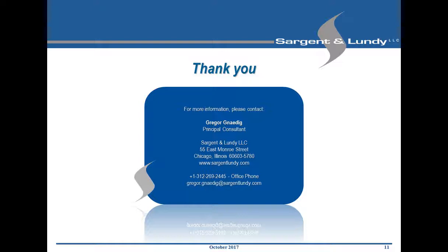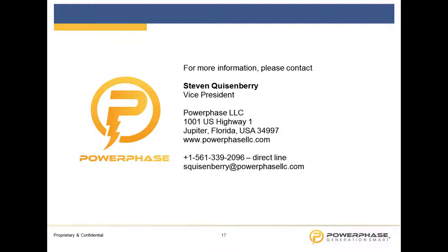Okay, great. If we just switch back to you, Steve, the question is, how many installations with F-class gas turbines have you done? Sure. So the first F-class install was in Saudi Arabia, 7FA .03 DLN 2.6 with a Mark 6E controller in simple cycle. And that was the first one, and that was done to obviously show the client in that region that the Turbophase, which is designed as a 30-year industrial piece of equipment, operates up to 55C ambient conditions. Subsequent F-class installs, we currently have 3 in process, which, because they're not commissioned, I can't share with you where they're at, but there's 3 more ranging from GE and Siemens equipment.